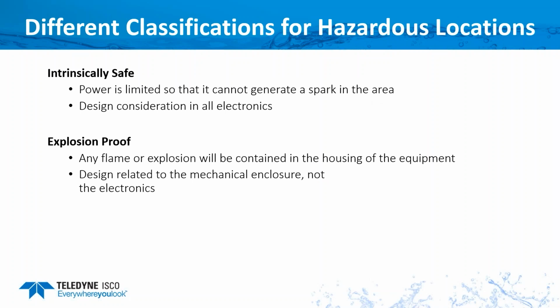Now, among the different classifications for hazardous locations, you're going to hear intrinsically safe, where the power is limited so it cannot generate a spark. And the design of the electronics is taken into consideration. What that means is that if the instrument was cracked open for some reason, it still would not produce enough current to create a spark. So even if you dropped a screwdriver inside the unit, it would not create a spark. So with no spark, there's no explosion.